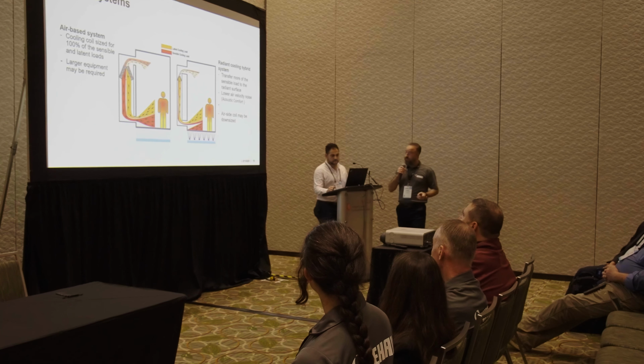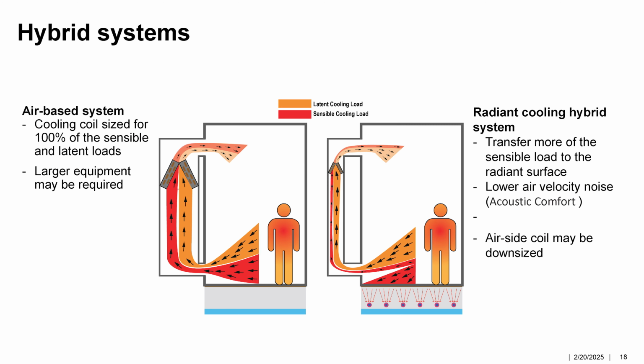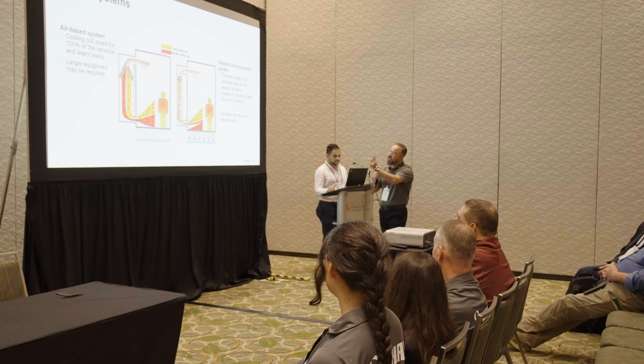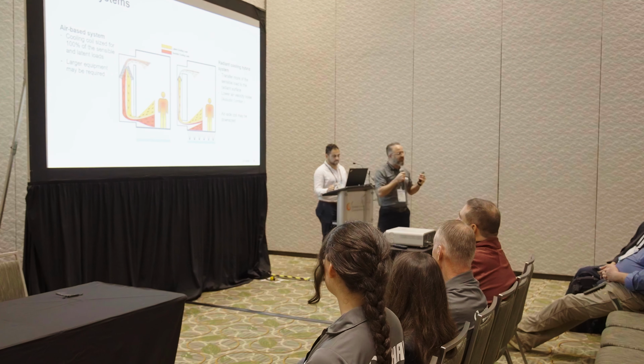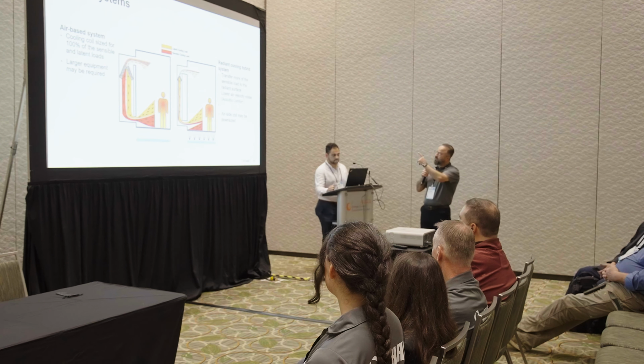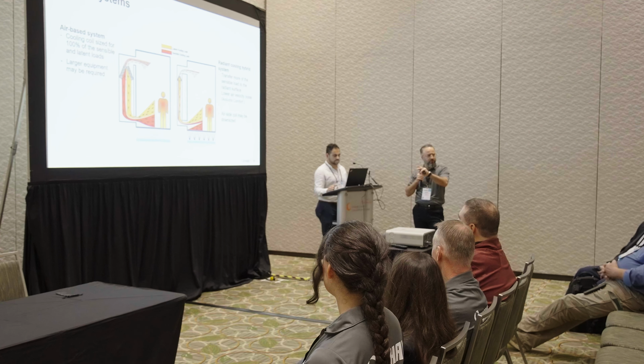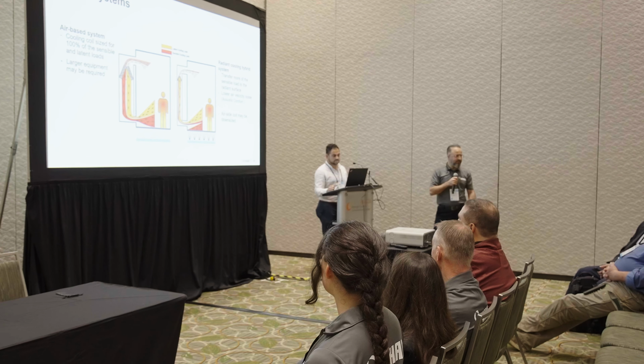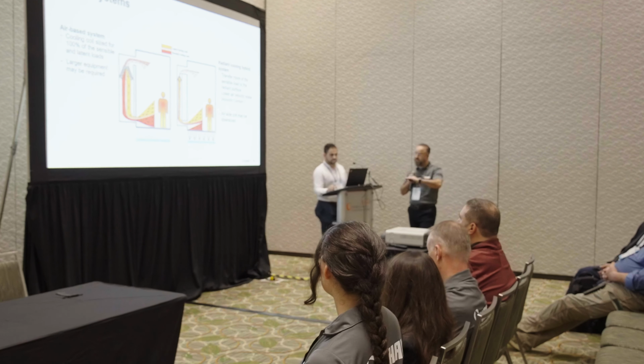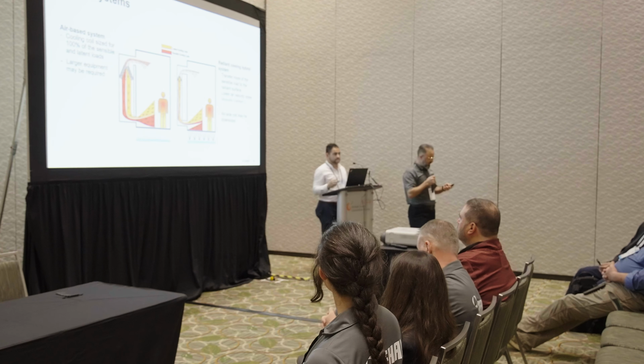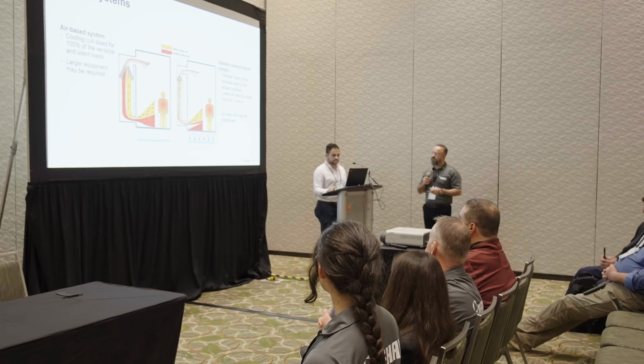Another thing we can do with a radiant cooling application is minimize your filtration and your ductwork. Again, this follows that topic of opening up the space for architects. That's why architects normally love this system. And the fact that you're using a smaller air system helps with the air velocity noise and everything. And that can provide 1 or 2 points on the WELL or the LEED certification, what they define as acoustic comfort. So all these topics that I mentioned are about the comfort that is achieved by a hybrid radiant cooling and air system.